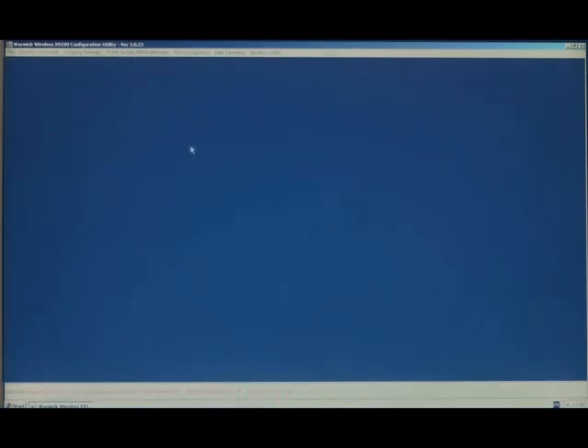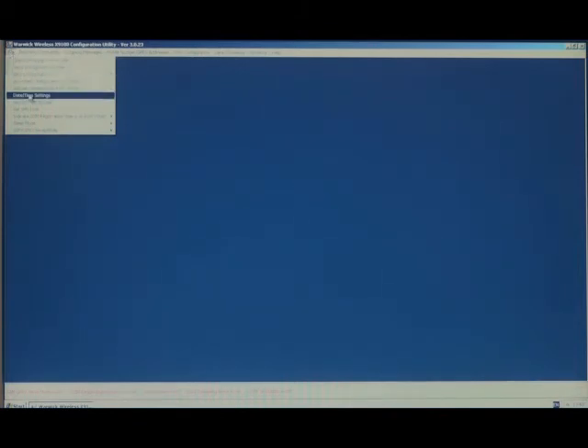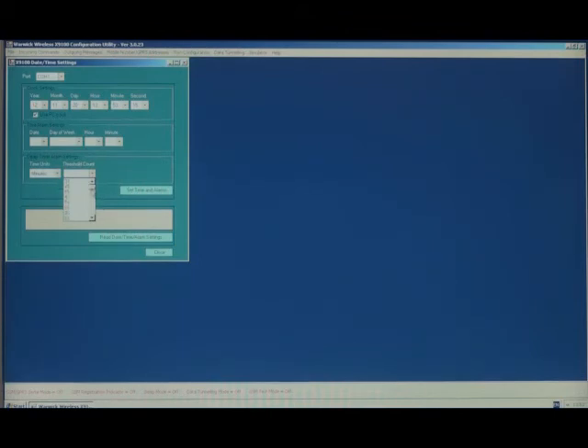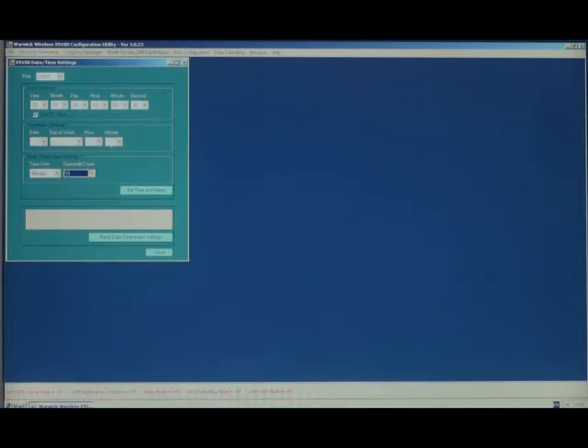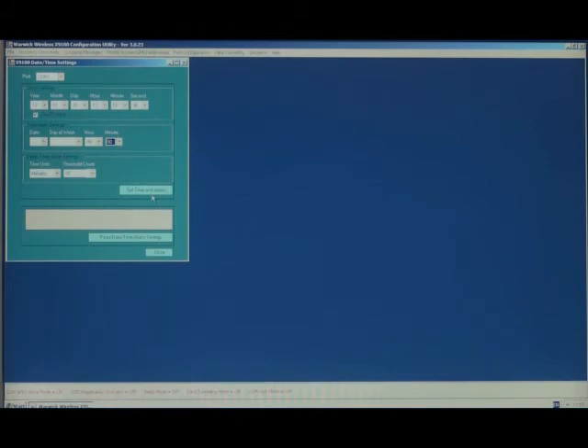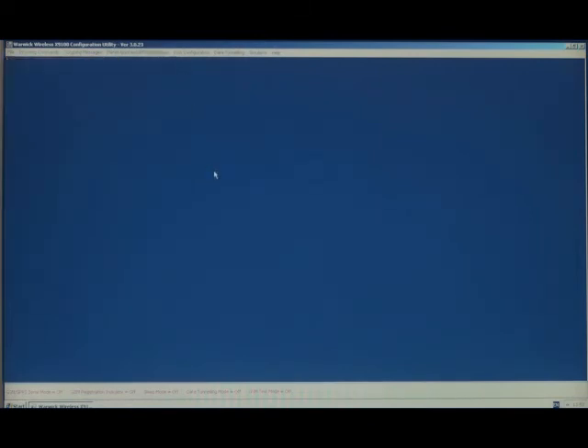Now once the configuration is complete, the PC that this has been running on is connected via the PC programming cable to the X9100. And the date time settings can be set. For our delay time, we can set it at 15 minutes. And to send the contents of the log to the website every 24 hours, we could say we'd send it at midnight, which would be 00. Then clicking on set time and alarms will download these values along with the current time to the X9100.